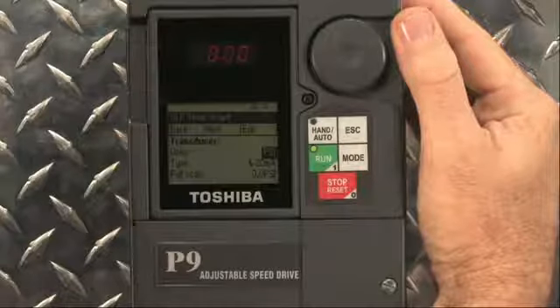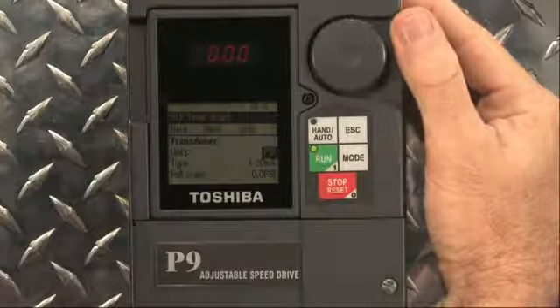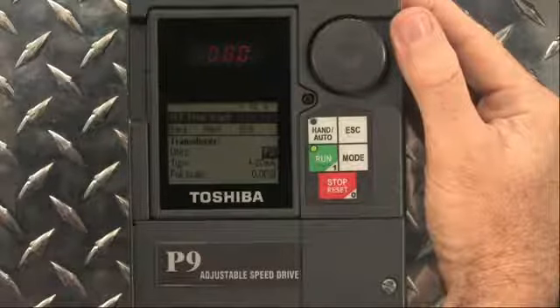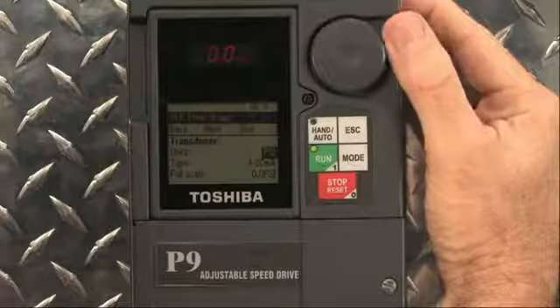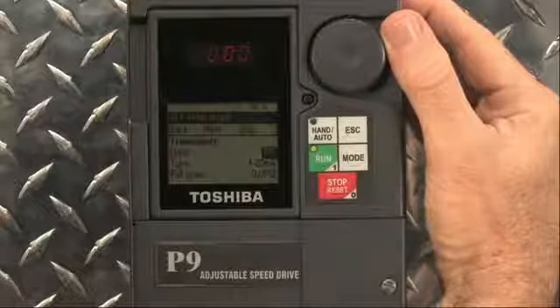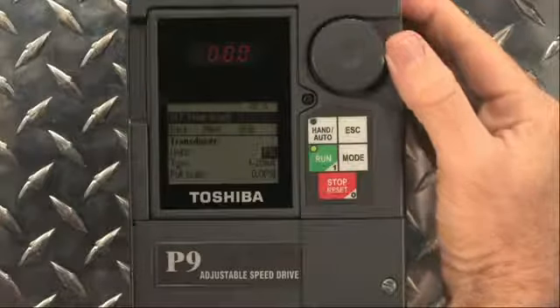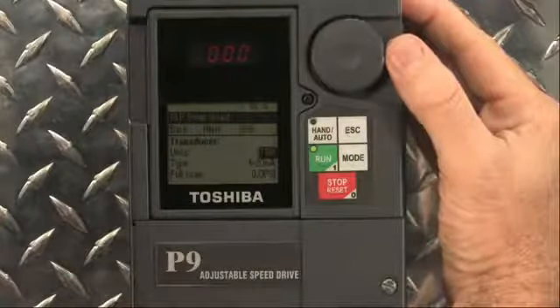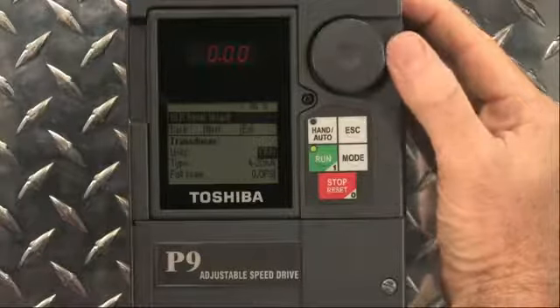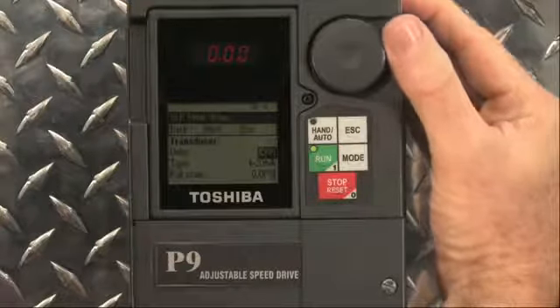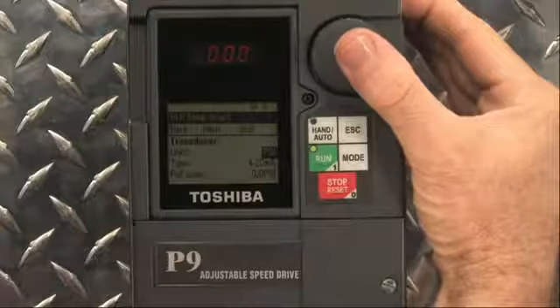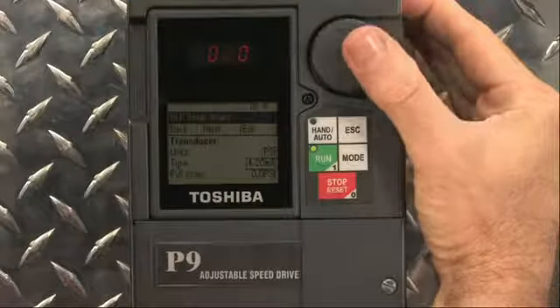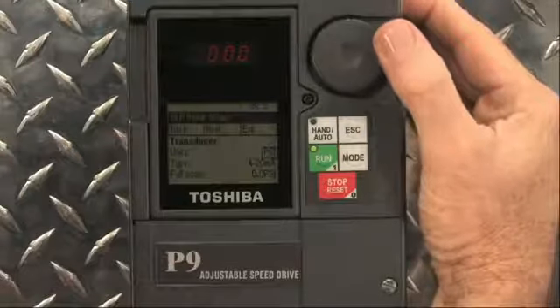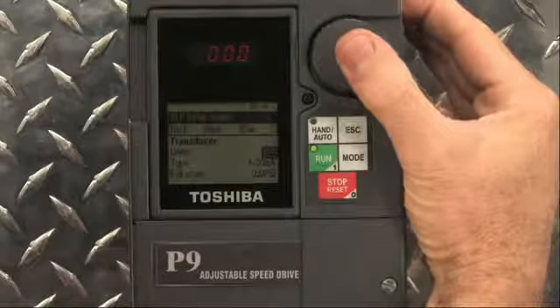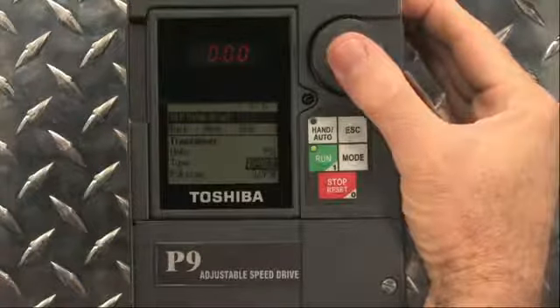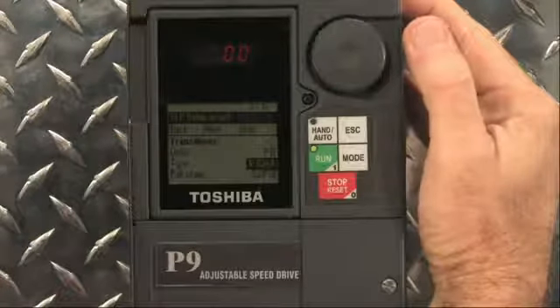For this demonstration, a 4 to 20 milliamps transducer is used. Let's begin by entering the units the transducer measures. This is a pressure transducer, so we will choose PSI. Other unit options are GPM, SCFM, degrees F or C, inches of water column, and feet of water column. Now we need to input the type of analog signal this transducer produces. The options are 4 to 20 milliamps, 0 to 20 milliamps, 0 to 10 volts, or 0 to 5 volts. For this transducer, we will select 4 to 20 milliamps.